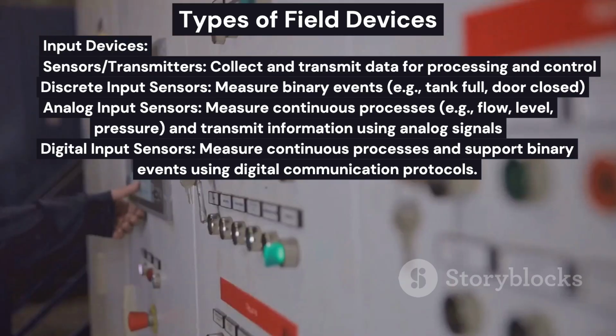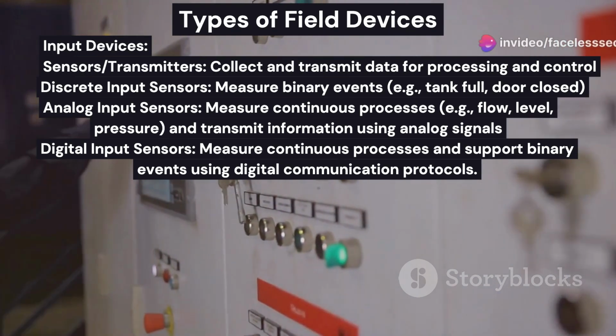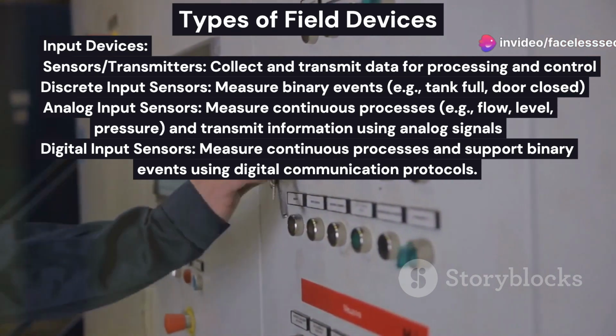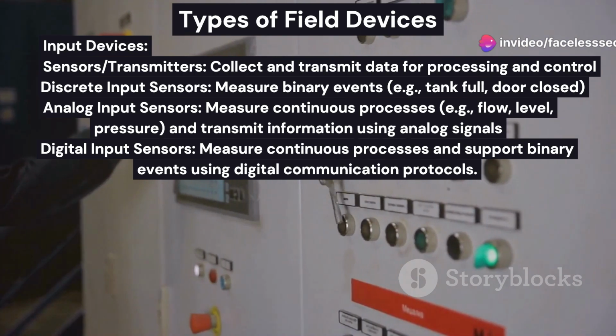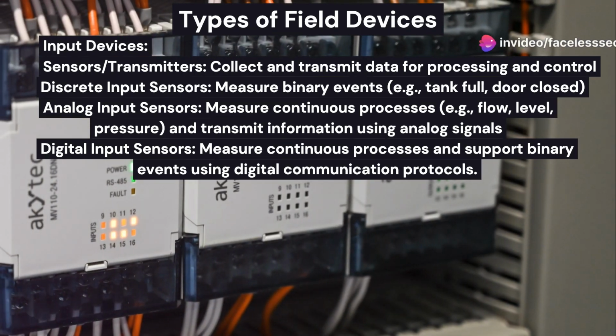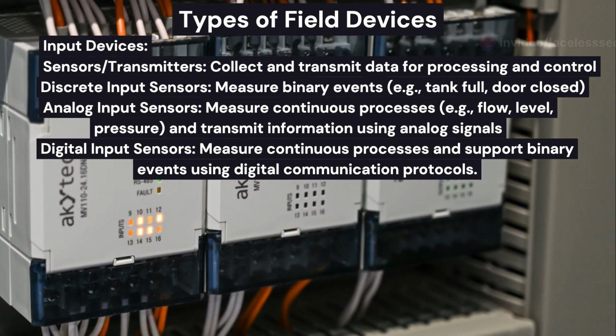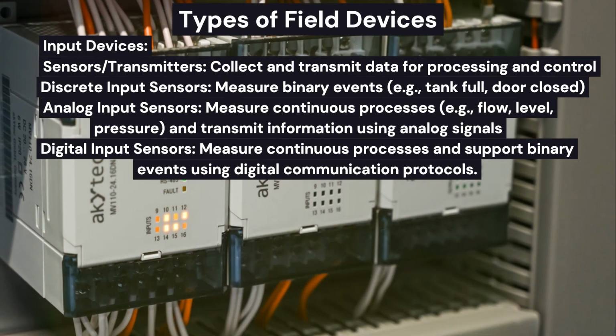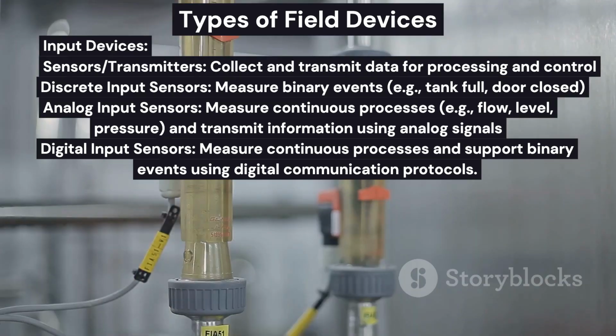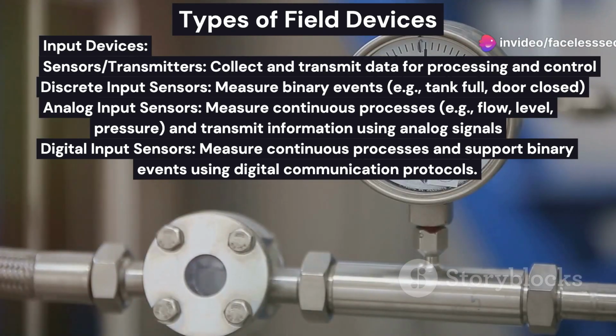Sensors and transmitters collect and transmit data for processing and control. Discrete input sensors measure binary events, such as a tank being full or a door being closed. Analog input sensors measure continuous processes like flow, level, and pressure and transmit information using analog signals. Digital input sensors, on the other hand, measure continuous processes and support binary events using digital communication protocols.